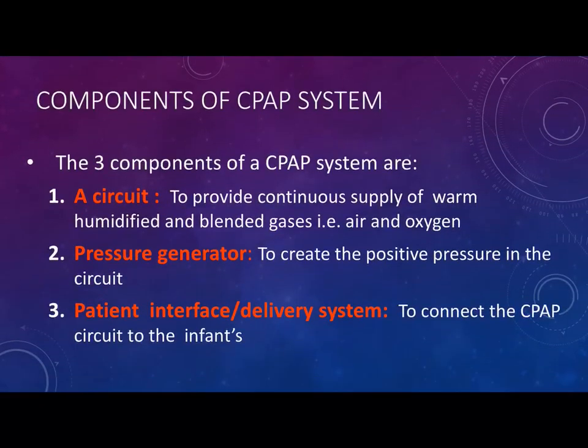After reviewing the effects of CPAP, we need to know the components of the CPAP system. We have three components. The first is the circuit, to provide a continuous supply of warm, humidified, and blended gas. The second is the pressure generator — the method to generate the CPAP pressure. The third is the patient interface, which is the method to connect or deliver the pressure from the circuit to the baby.